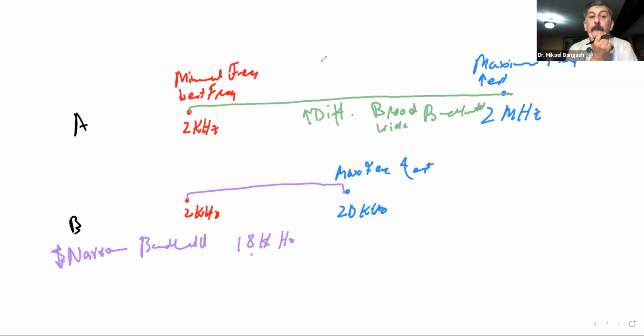Just because this one had a low frequency, the minimum frequency was the same. That doesn't make these transducers low frequency or low bandwidth transducers. Because the bandwidth depends on the difference between the minimum and the maximum. The greater the difference, the greater the bandwidth. Is that clear, girls? Lower the difference, lower the bandwidth.